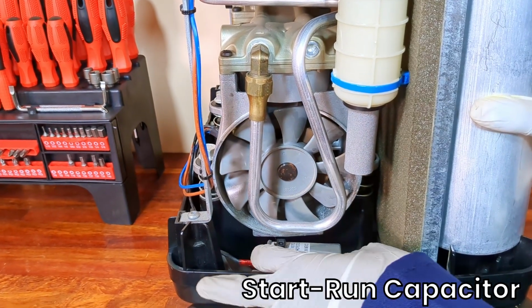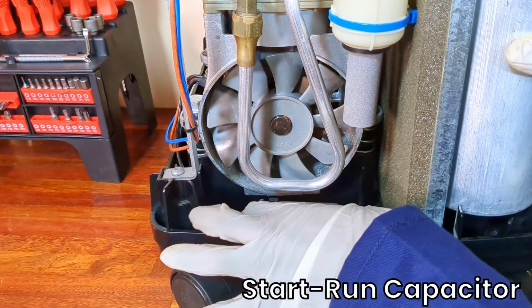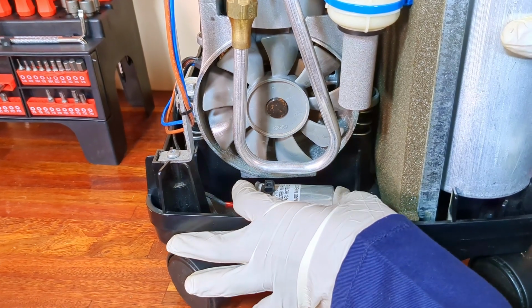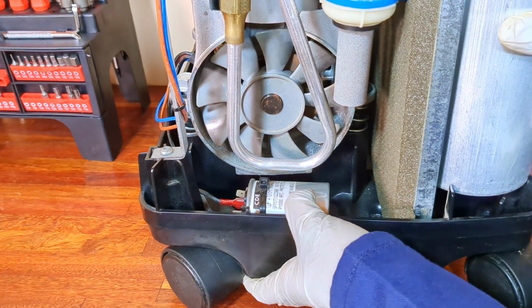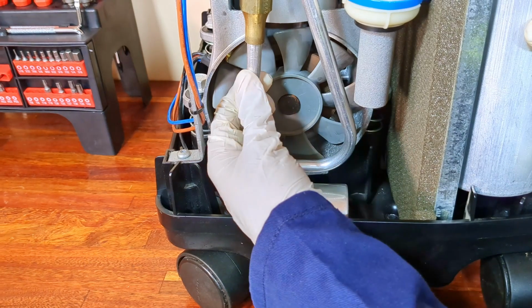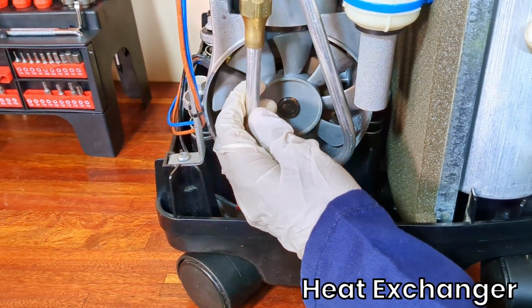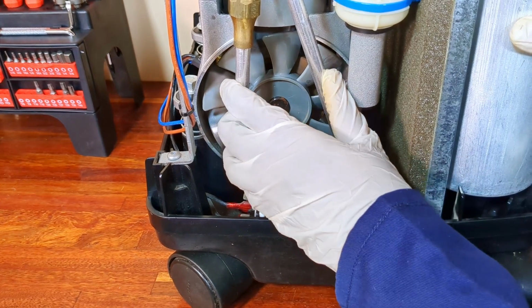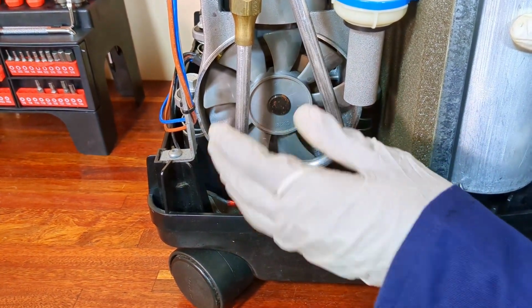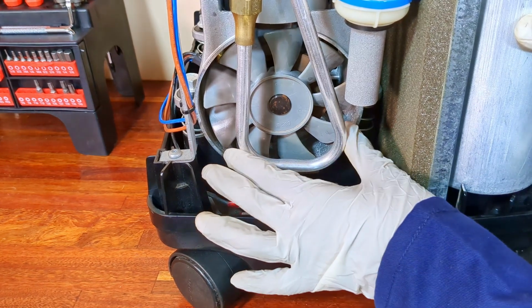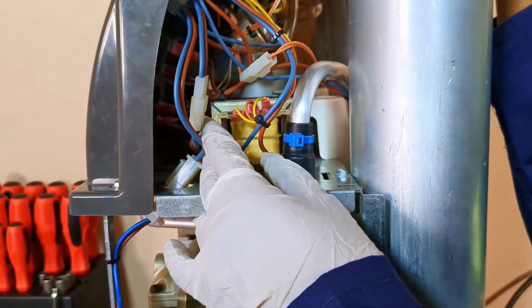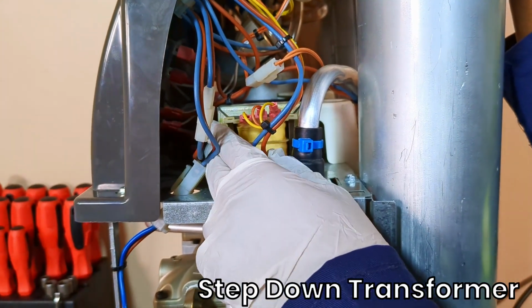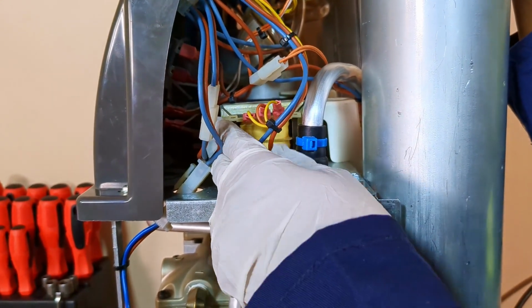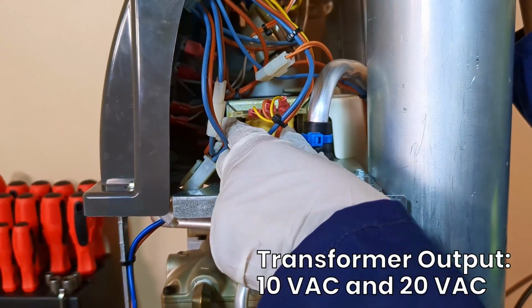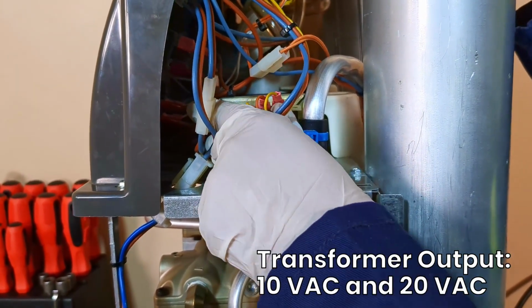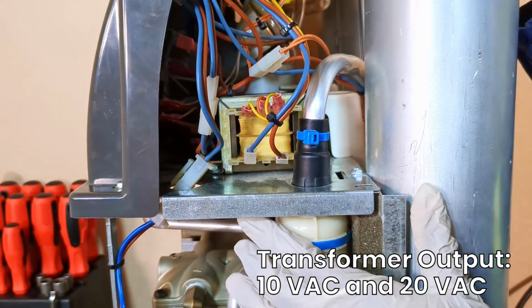Right here we have a start capacitor. This is crucial to help the compressor motor to start up, and it is a 10 microfarad capacitor. Connected to the compressor here is a heat exchanger, and this heat exchanger is used to lower the temperature of the compressed air before it enters the solenoid valve. This is a transformer. This transformer steps down 120 volts AC to lower output voltages that are required by the electronic components on the board as well as the valves.